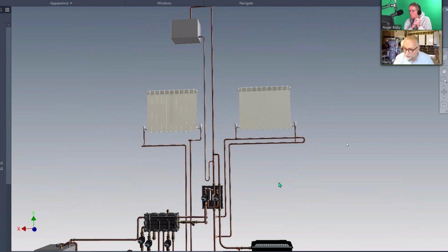Just tell me what happens if we didn't put that cold feed with that little drop loop. If you just put it like I have so many times, just straight up, that means that you've got hot water rising into the feed and expansion tank. It's going to be releasing air from the system as it goes. What's the harm in it?